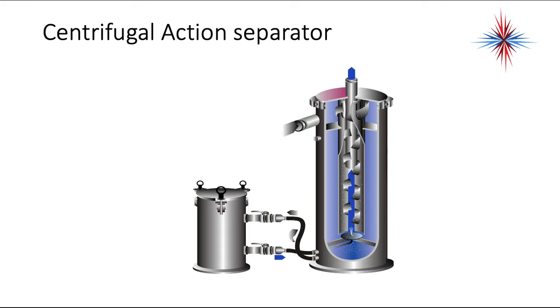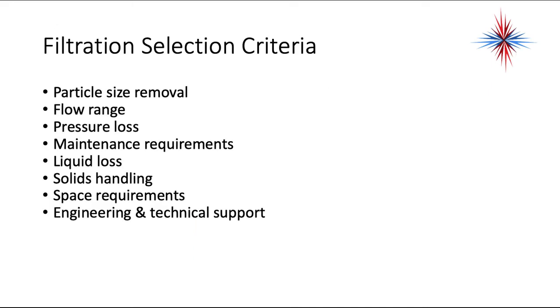Centrifugal action: if you spin something, centrifugal force will pull the heavier objects outward — that's what we're doing with the solids, which are heavier than water. For filtration selection, you have to look at particle size removal, flow range, pressure loss, maintenance requirements, liquid loss, how solids are handled, space requirements, and engineering and technical support.